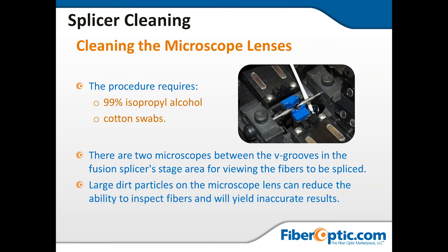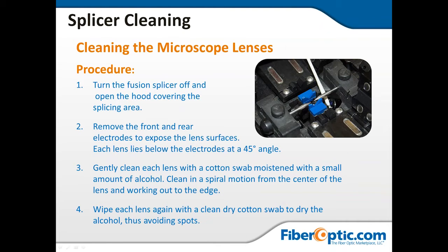Cleaning the microscope lenses is very important. 1, turn the Fusion Splicer off and open the cover to reveal the splicing area. Remove the front and rear electrode to expose the lens surfaces. Each lens lies below the electrode at a 45-degree angle. Gently clean each lens with a cotton swab, moistened with a small amount of alcohol. Clean in a spiral motion from the center of the lens and working out to the edge. 4, wipe each lens again with a clean, dry cotton swab to dry the alcohol, thus avoiding spots.